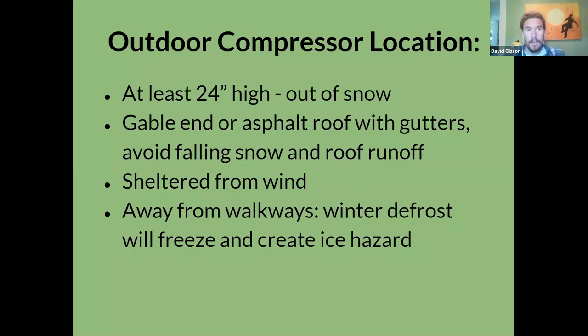In terms of locating the compressor outside, there's some important considerations to keep in mind. In Maine, it should be at least 24 inches high, potentially higher off the ground up in the county where you get more snow. But the idea is that it's completely out of the snow in the wintertime. If it's mounted too low, then it can freeze and just freeze itself shut and stop working. And I've heard of that happening, particularly for heat pumps that were just mounted directly on the ground.